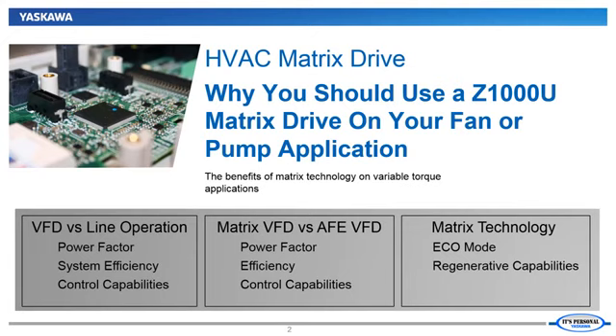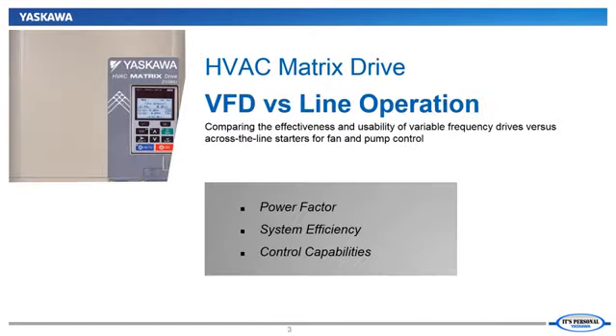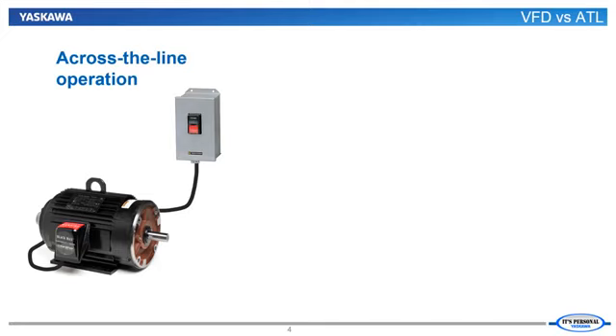Once we understand how the Matrix works, we can understand how both the eco mode function and the inherent regenerative capabilities can be beneficial to fan and pump applications. Our first job is to consider and evaluate the use of a variable frequency drive, or VFD, versus just running the fan or pump using an across-the-line starter. An across-the-line starter can only apply full voltage and 60 Hz frequency to the fan or pump motor. Any changes to pressure or flow will need to be made using either dampers or inlet guide vanes for fans, or valves for pumps.